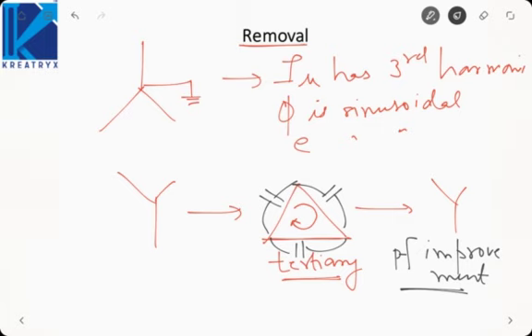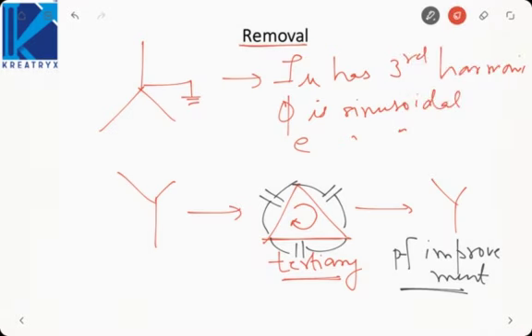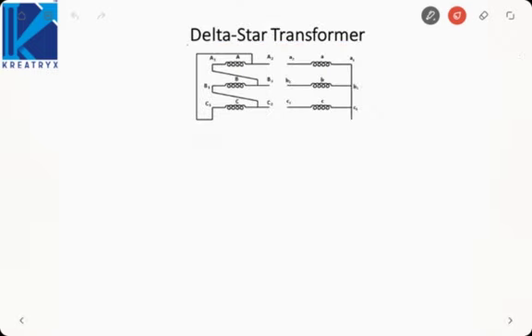And how to remove this? By grounding the neutral or by connecting a tertiary winding. Otherwise the neutral point is floating, due to which the load experiences fluctuation in the voltage. So we cannot connect a single phase load across a star-star transformer. Let's move on to our next connection, which is the delta star transformer.